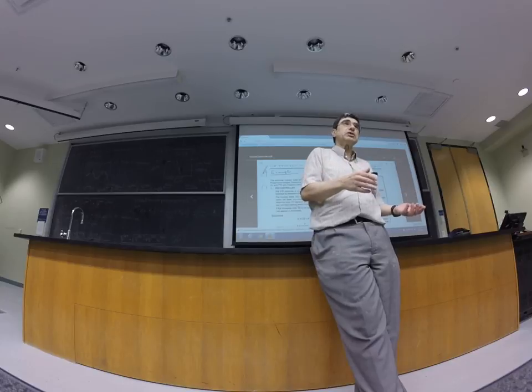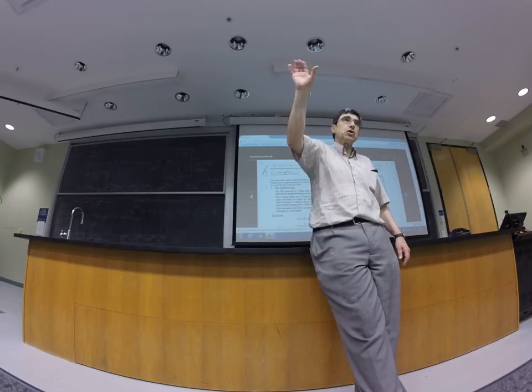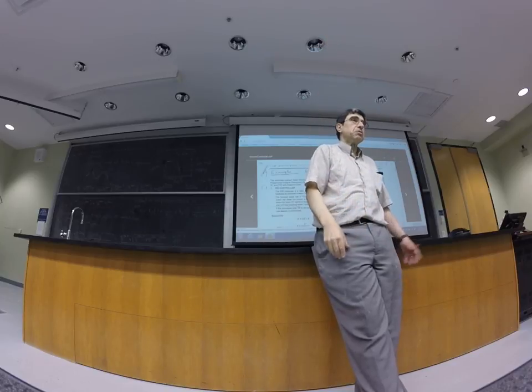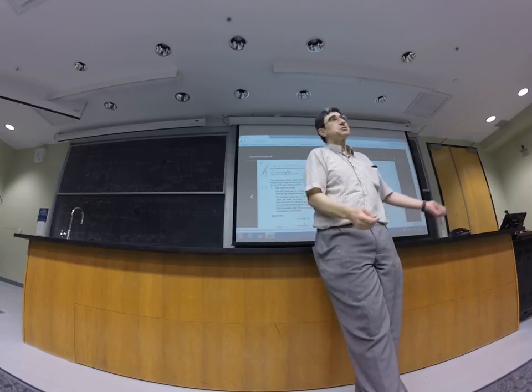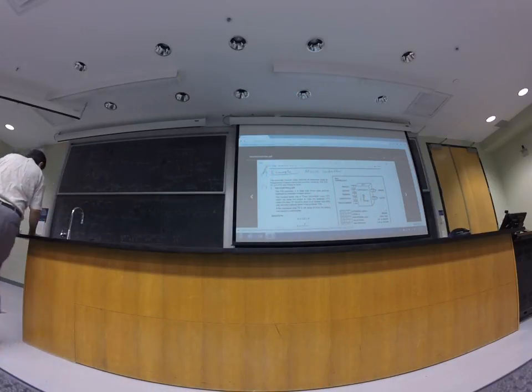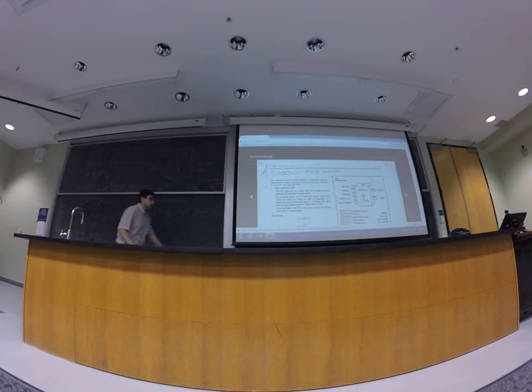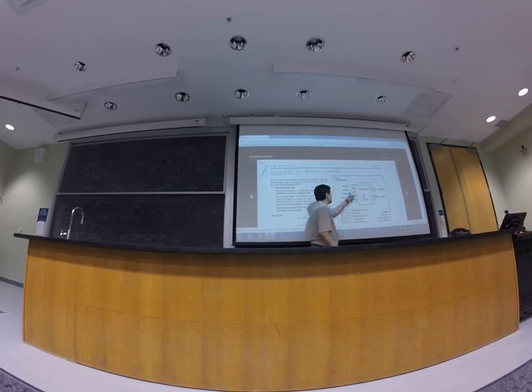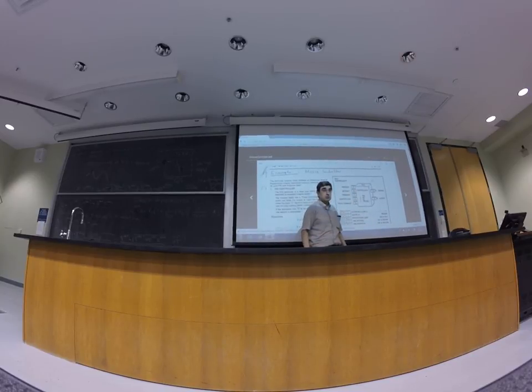So in such a situation, the master controller for the level, the operator will change it. But the slave controller needs to get an electronic signal. That's why S, the set point, can be coming from the wire. So that will be wiring from the master controller to the slave controller. Clear, everyone?